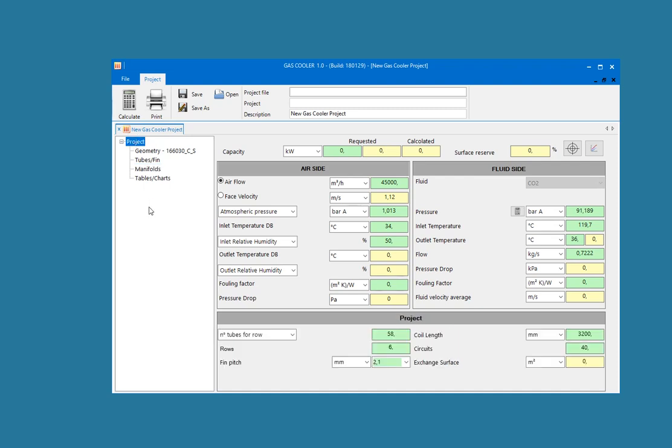During the cooling of CO2 gas, since you are in a transcritical zone and you have a significant thermal shift, the physical properties of the gas change a lot between the beginning and the end of the cooling.